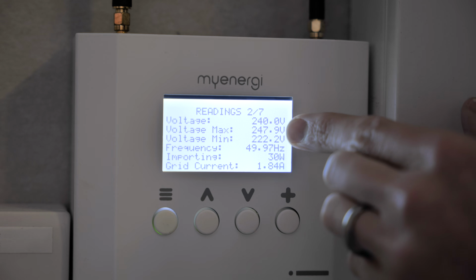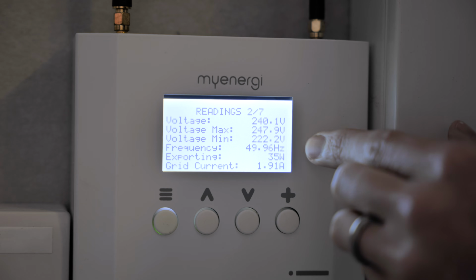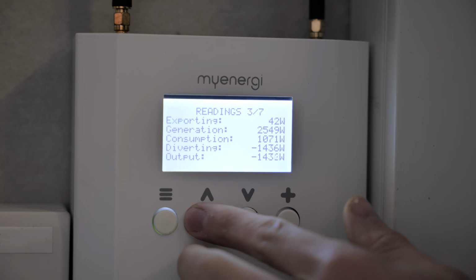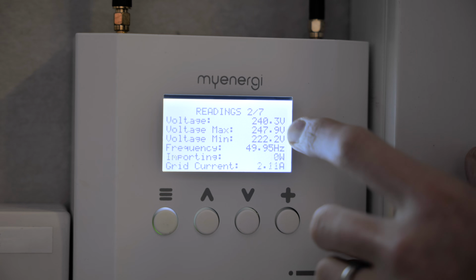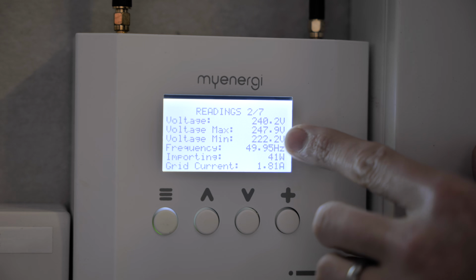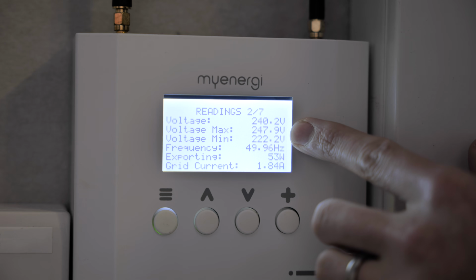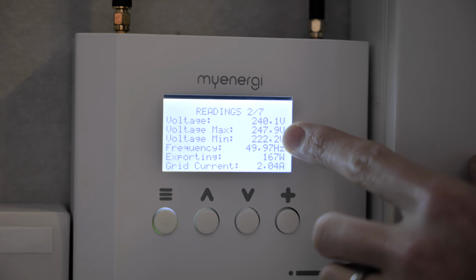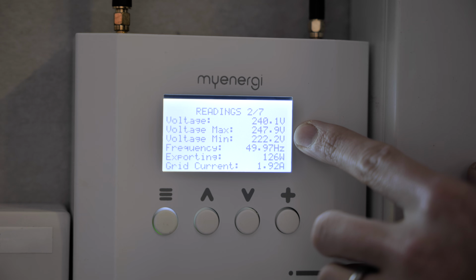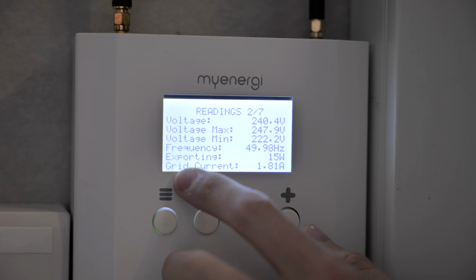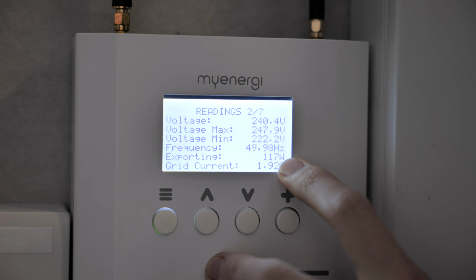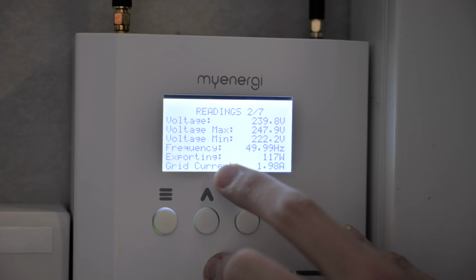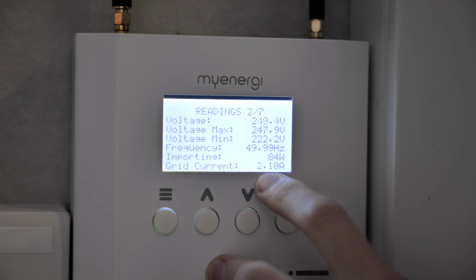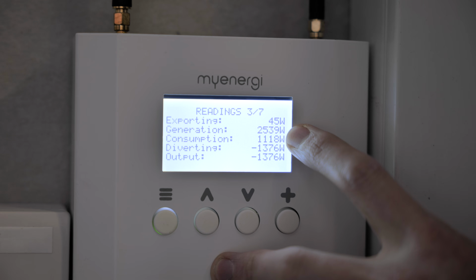And so going to this little section here will allow you to look at it and go, okay, well, we're hitting 260. It might only happen for a second, but it's happened, and the battery would fault out in that case, or it might drop to 200 volts, and the same thing would happen, and this will log it. So that's a really good reference point there. We've then got frequency around 50 hertz that we normally would see. We're now exporting again, 117 watts, and then we've got a grid current of 2. We can see our generation again.